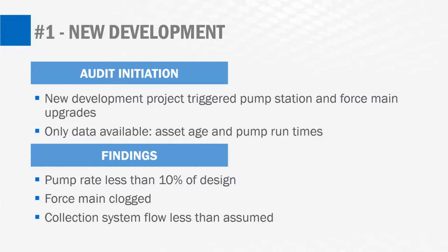For our first case study, a new development was being proposed that would require capacity at an existing pump station. So the audit was initiated in order to gather data to determine what those upgrades would need to be. Before the audit was performed, the only data available were the asset age and pump run times. The pump run times were primarily used to determine that upgrades were going to be needed. The pumps were running about 14 hours per day, both pumps that is, which was pretty significant. So the determination was that this pump station was out of capacity and upgrades were almost certainly required.